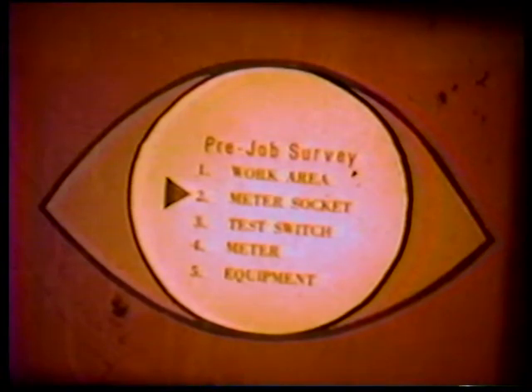Now, inspect the meter socket. Be sure the socket is company approved. Is the wiring within the meter socket in good condition? In new installations, check for nicks and cuts in insulation of the wire that would allow possible short circuits. Be sure all connections are tight.